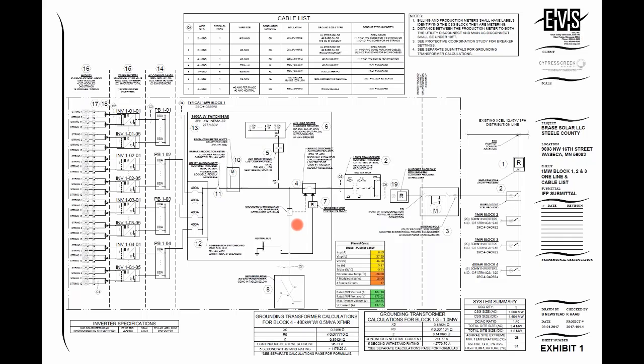We had a grounding transformer breaker. So that's a breaker that's connected to the load bus of the switchboard down to a zigzag transformer. And they actually threw, even on this one, a protective relay. So they had a grounding transformer breaker. It went down to the transformer, and they had a protective relay to the main AC disconnect.